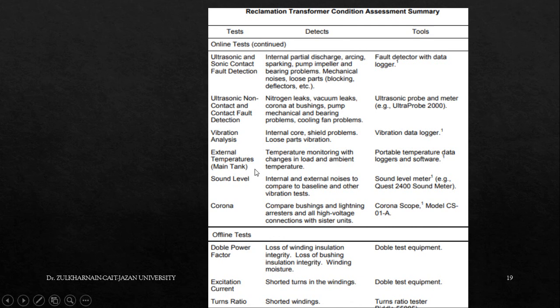Similarly, the temperature can also be checked in different ways. Sound level, if there is a screeching voice, you can check for that. And similarly, there are also corona, bushing and lightning arresters. These are the devices here which can be checked for different problems. So all these are online tests, and offline tests are Doble power factor by just calculating and checking practically. Excitation current, turns ratio, these are the offline tests that you can check.